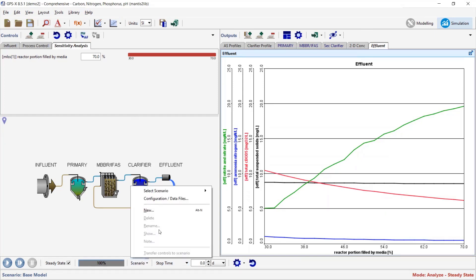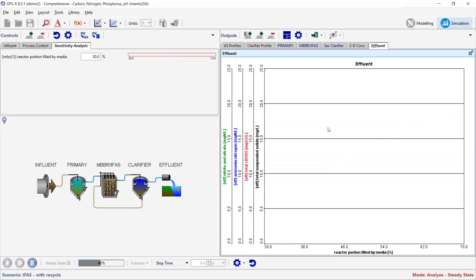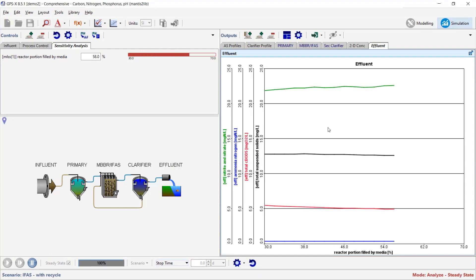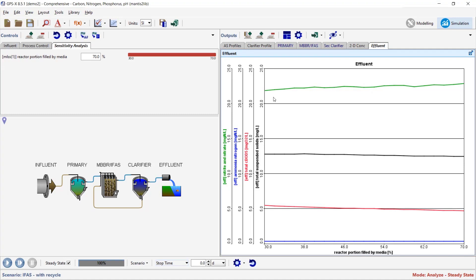Let's rerun that in an IFAS context to see how it looks different. With the RAS recycle on, there isn't a lot of difference across fill fractions because even at 30%, the system was already doing full nitrification. It doesn't change very much across the range — going down only a little from right to left — and without an anoxic zone this particular setup doesn't allow for much denitrification.